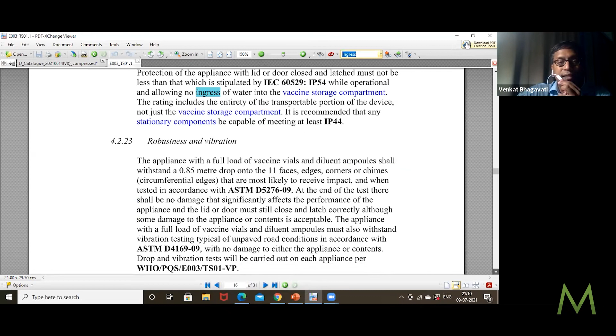This is the test which they have mentioned for robustness and vibration, which is an ASTM standard. This is again a slight anomaly I can observe here, because ASTM standards are mostly used in the US, and labs outside the US are very rarely accredited for them. So instead of mentioning the ISO or ISO IEC standard for vibration and shock, they have gone back to using ASTM standards.